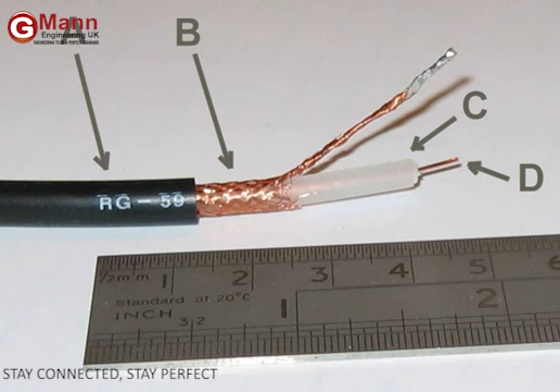The gaps or holes allow some of the electromagnetic field to penetrate to the other side. For example, braided shields have many small gaps. The gaps are smaller when using a foil solid metal shield, but there is still a seam running the length of the cable. Foil becomes increasingly rigid with increasing thickness, so a thin foil layer is often surrounded by a layer of braided metal, which offers greater flexibility for a given cross-section. Signal leakage can be severe if there is poor contact at the interface to connectors at either end of the cable or if there is a break in the shield.